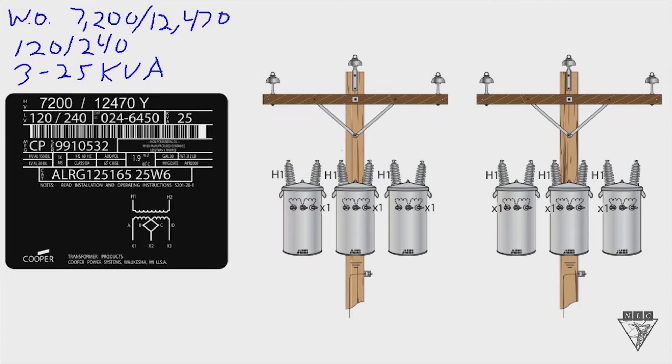So compare this with our transformer nameplate and on the high voltage rating of the transformer we've got a match because we've got 7200 volts which matches the phase to ground connection on our circuit voltage.